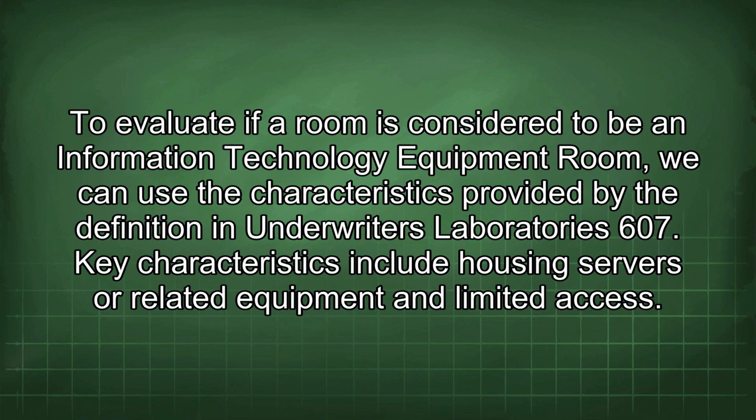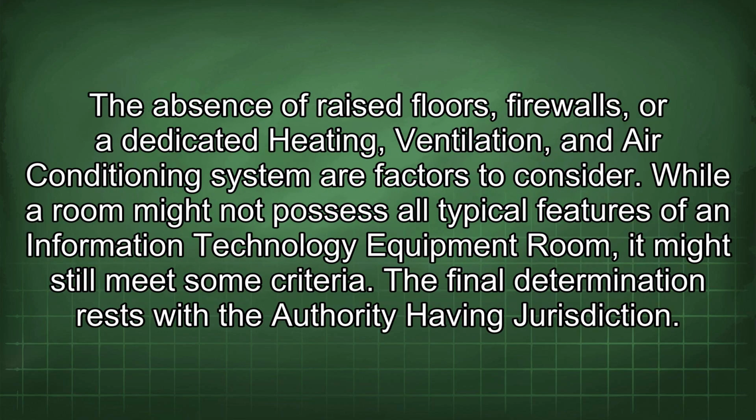Key characteristics include housing servers or related equipment and limited access. The absence of raised floors, firewalls, or a dedicated heating, ventilation, and air conditioning system are factors to consider. While a room might not possess all typical features of an information technology equipment room, it might still meet some criteria. The final determination rests with the authority having jurisdiction.